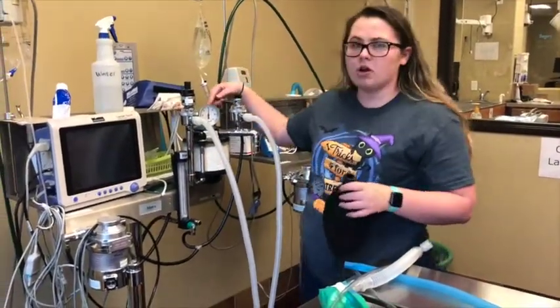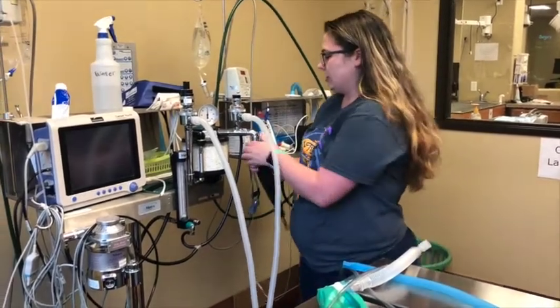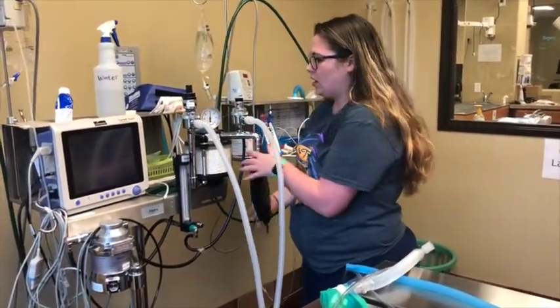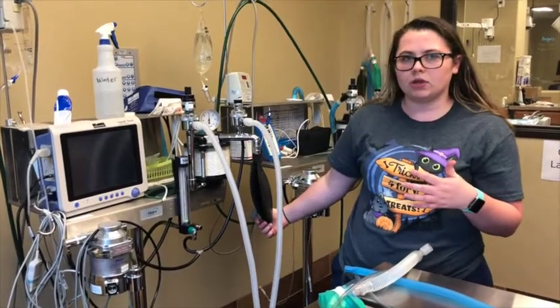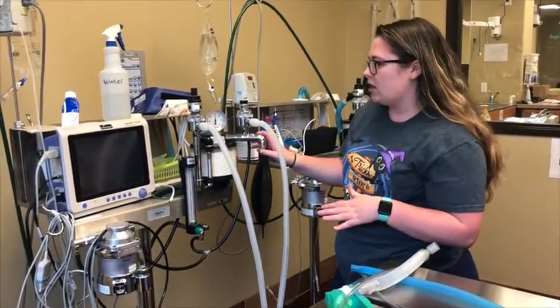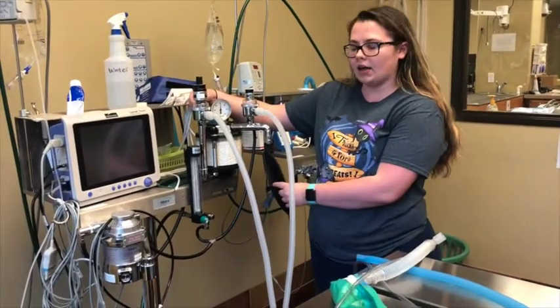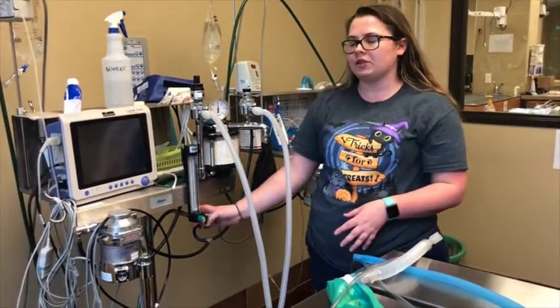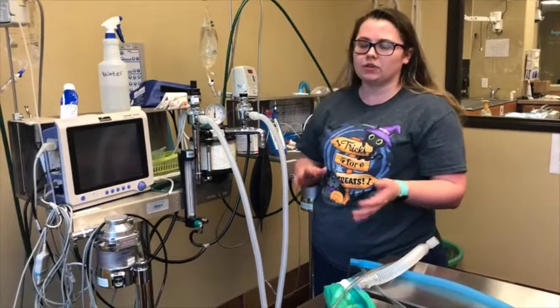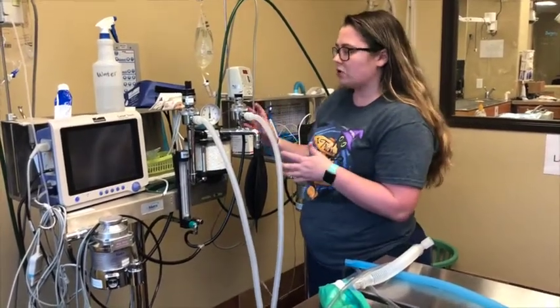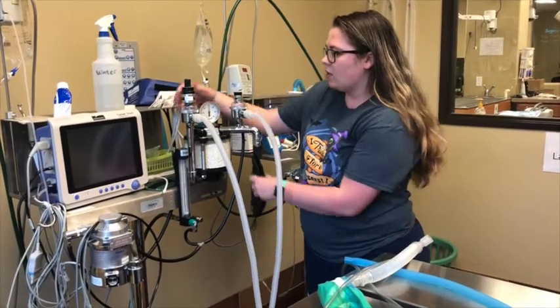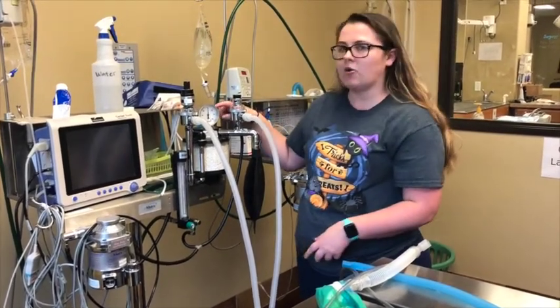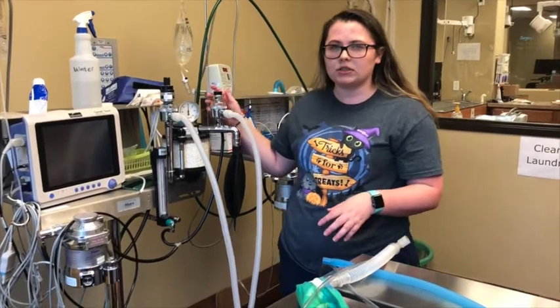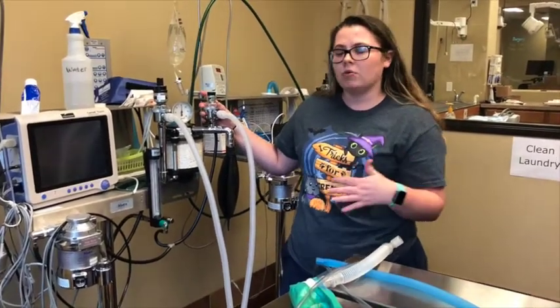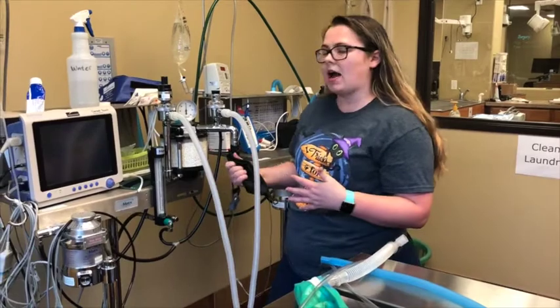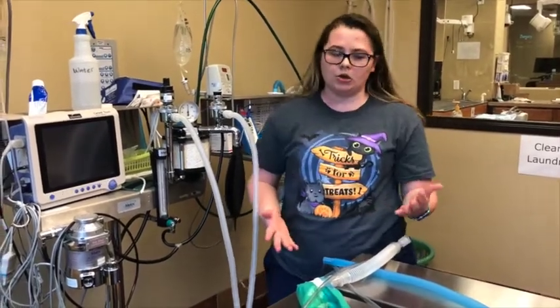So this right here is our manometer. It measures the amount of pressure that we give to our patients with our gas and our oxygen. This button here can fill the bag, as well as this button can fill our bag with oxygen. This is our rebreathing system. If we're going to be breathing for our patient, we would hold down and squeeze. We don't want this to go past 20 or 25 at the most, because then it would fill their lungs too much. We want the rebreathing system, when you squeeze the bag, to act like a normal breath that they would take on their own.